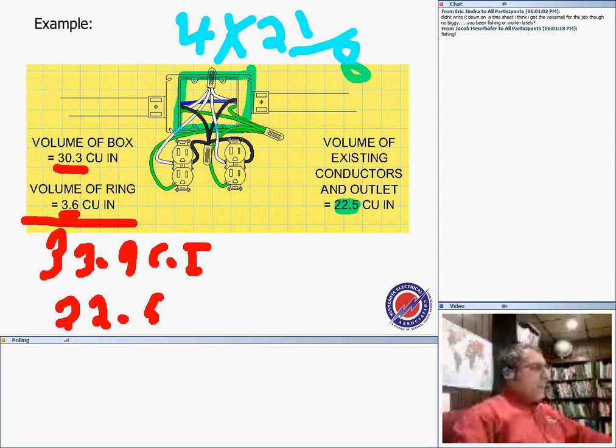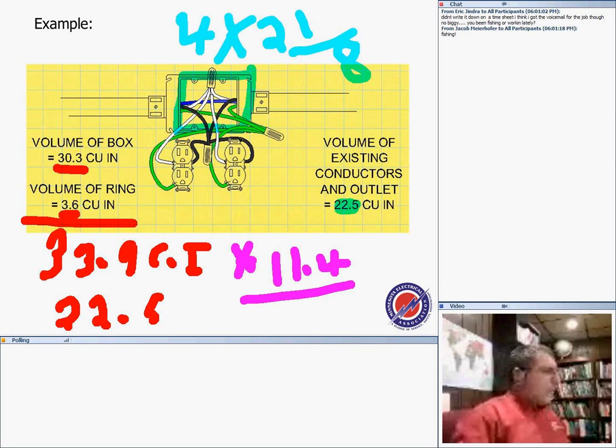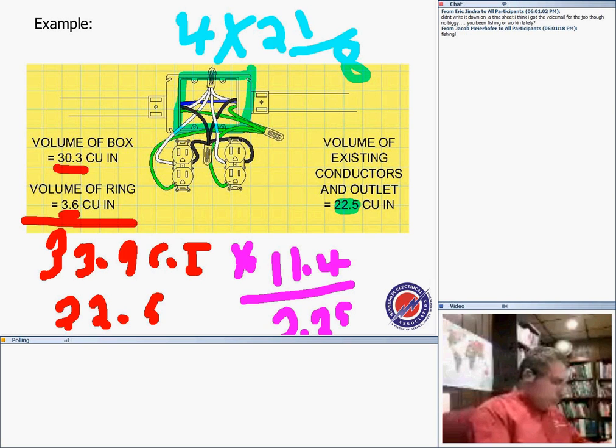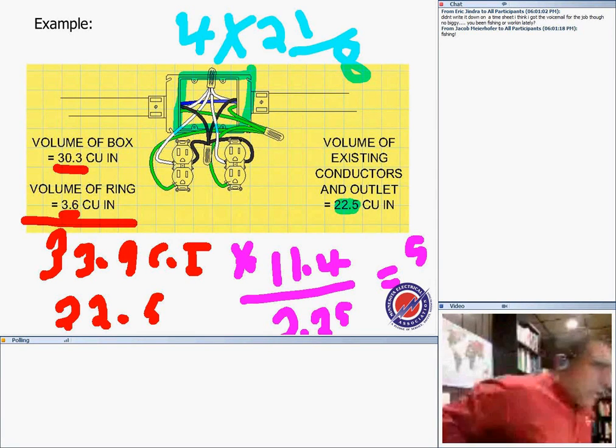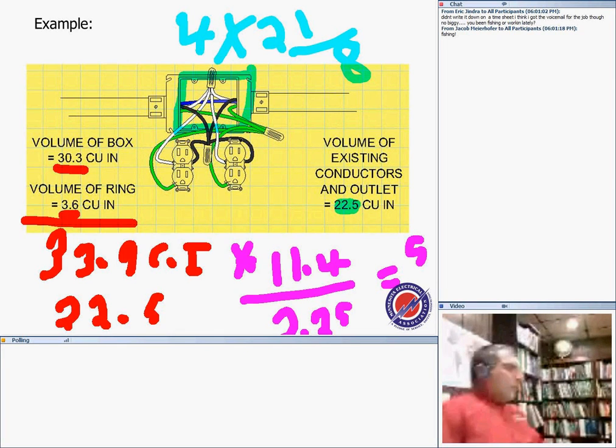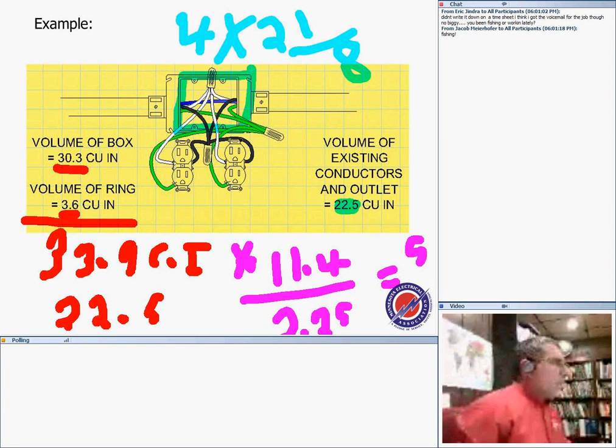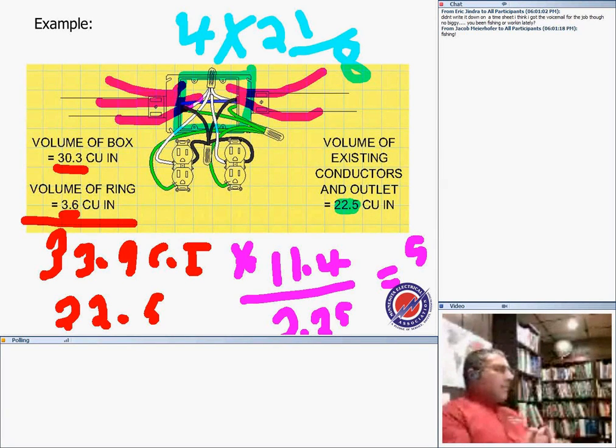I decided I'm going to be pulling conductors and terminating them, number 12 conductors. So take this number and divide it by the allowance for number 12, which is 2.25. 11.4 divided by 2.25 will give us 5 conductors. These are the extra conductors that I can pull through: 1, 2, 3, 4, and then 1 here, 5, coming in and terminated inside this box.